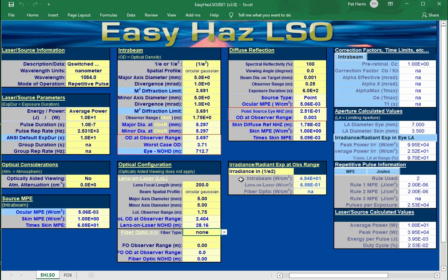If we're looking at the intrabeam, we'll want to go to 1 over E. Remember, barrier specs are in 1 over E. We would want something that would be about 90, we'll call it 100 watts per square centimeter, but if you told your vendor 90 watts per square centimeter, I think there are barriers that would be perfect for this at this distance. They're 100 watt per square centimeter barriers.